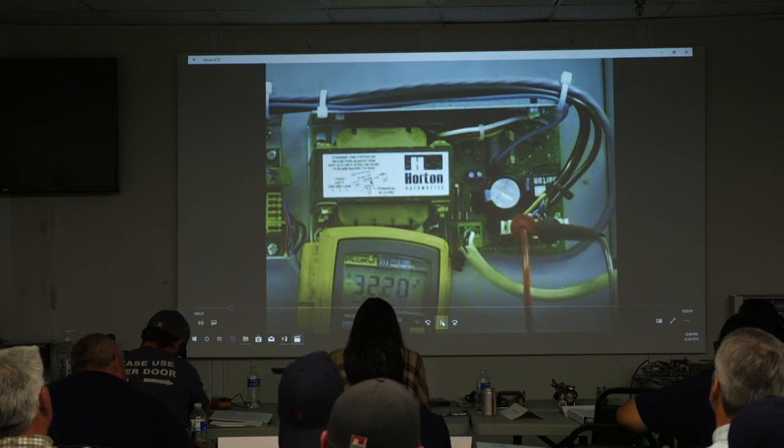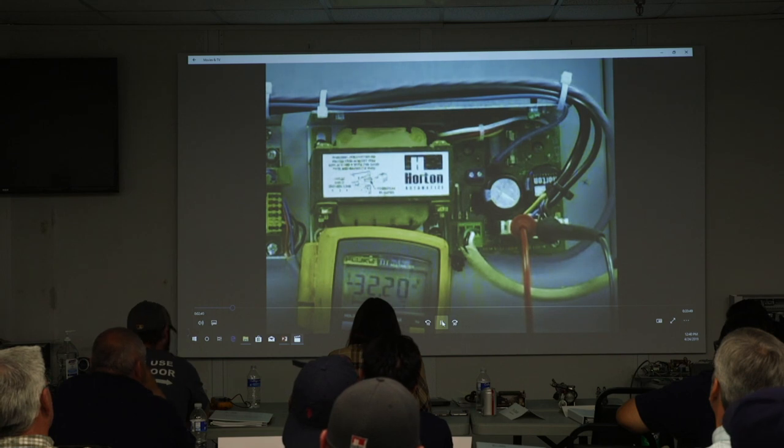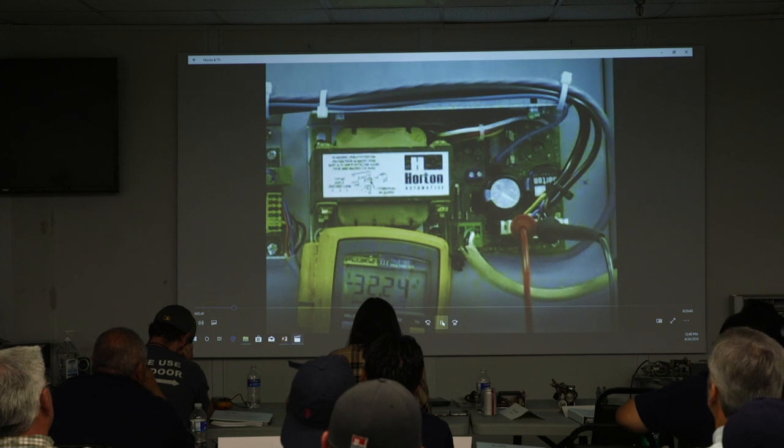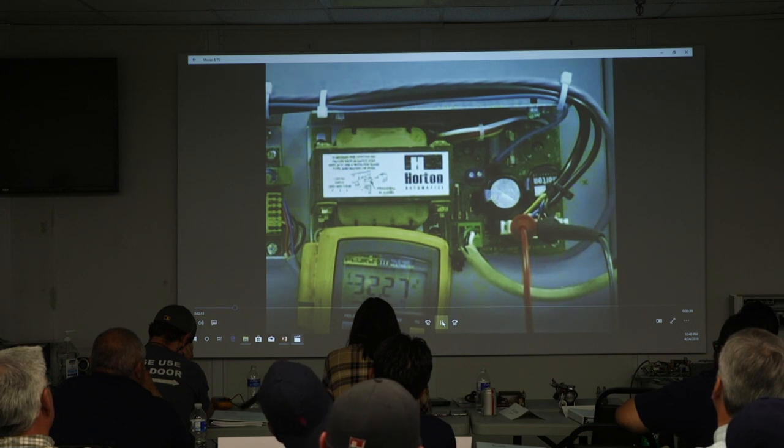To check the low voltage, insert the probes of a VOM meter set to DC voltage in the back of pins 3, red, and 4, black, of the connector. The meter should read between 27 and 32 volts DC. Testing the supply at these points is a shortcut to removing and testing the fuses. If either of these tests fail, the associated fuses should be checked.